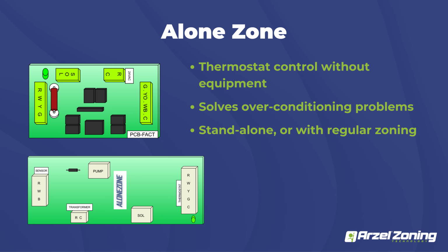And what that would allow is for that zone to still have dampers and a thermostat, but it would prevent that zone from ever calling on its own. So it would never be your smallest zone anymore. So you guys wouldn't have to worry about a really big bypass or maybe possibly avoiding a bypass in general if you could. So it gives you guys that capability as well. Also, the Fact board can act as a fresh air board, and you can add external controls to that. Or from us, if you have it pre-installed, it would just open anytime there's a call on the panel for fresh air. It would open that damper as well. So that's a use for it.